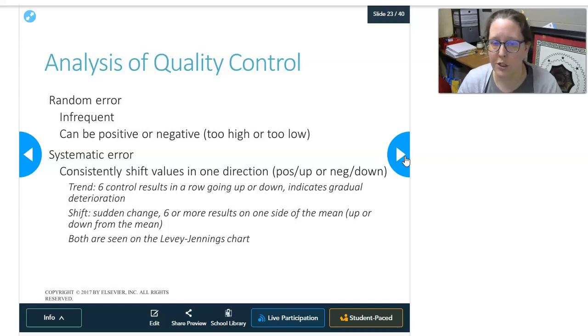A shift is a sudden change, so it means that you were at this level, and all of a sudden everything shifted, and now everything's at this level, or it shifted up or shifted down, and so you really see an abrupt change, and then everything's at this other level. These are often seen if you have a new calibration or a new reagent lot or something, and it caused a shift in the mean of your quality control. Both trends and shifts are seen on a Levey-Jennings chart. And so I'll show you what this looks like, and this is how you can see if you have a shift, a trend, or a random error.